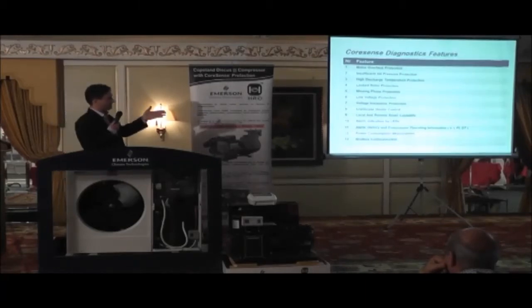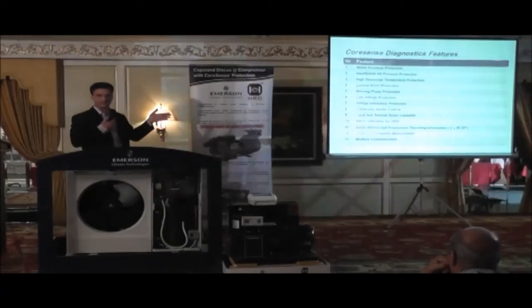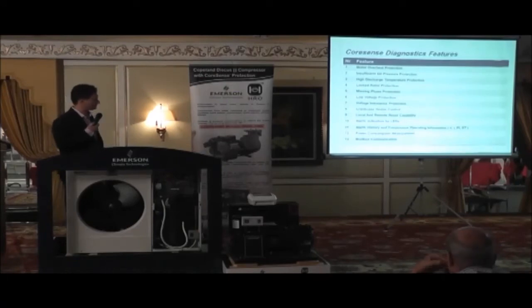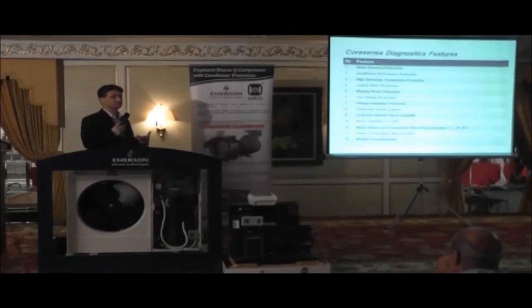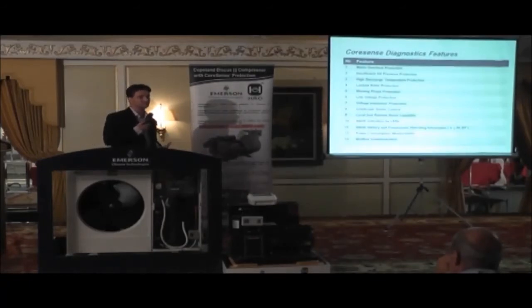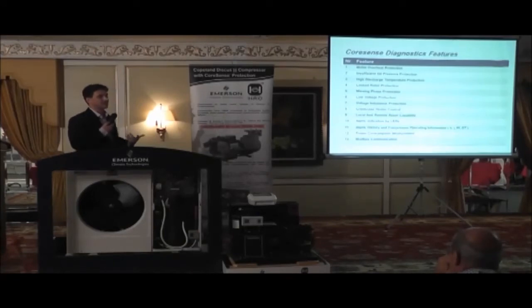We've made a relay addition to control the crankcase heater. I'll talk about that later. We've got alarm indication on the diagnostic module. So it will help the service technician. It will tell the service technician why the compressor is tripped. And then with the information that we supply, it will help him diagnose what the problem is in the system.